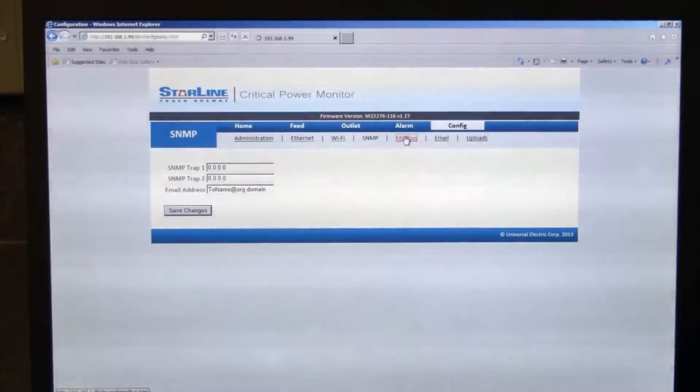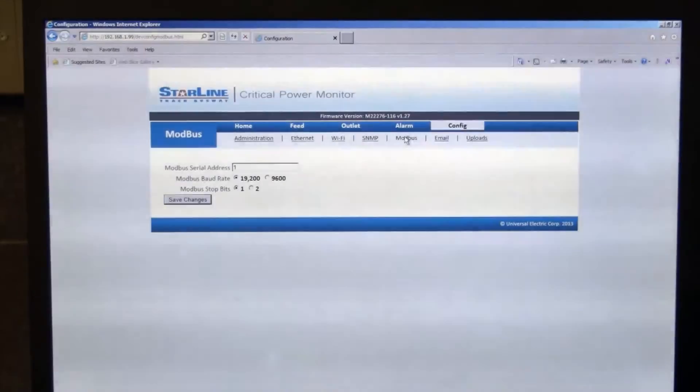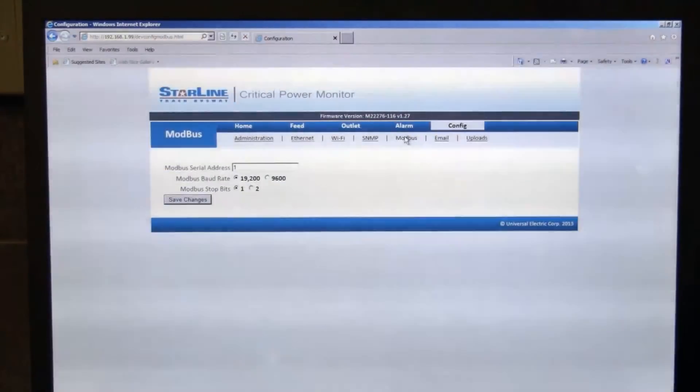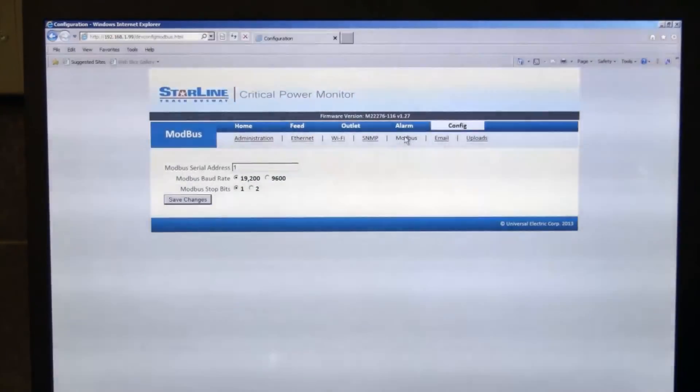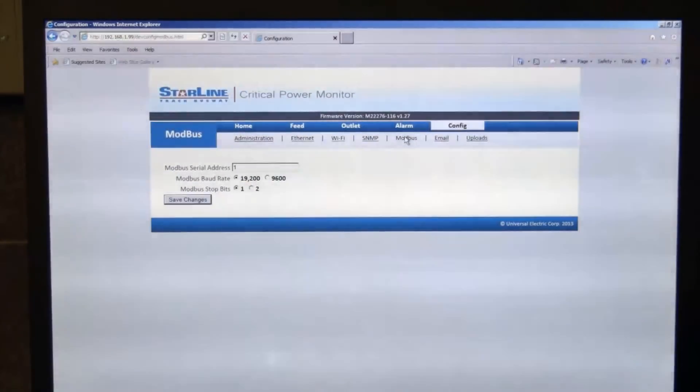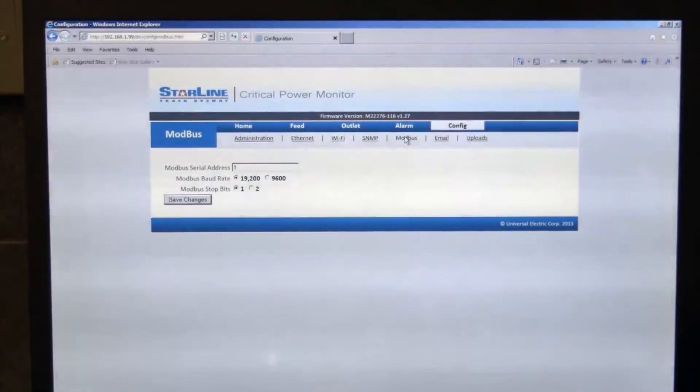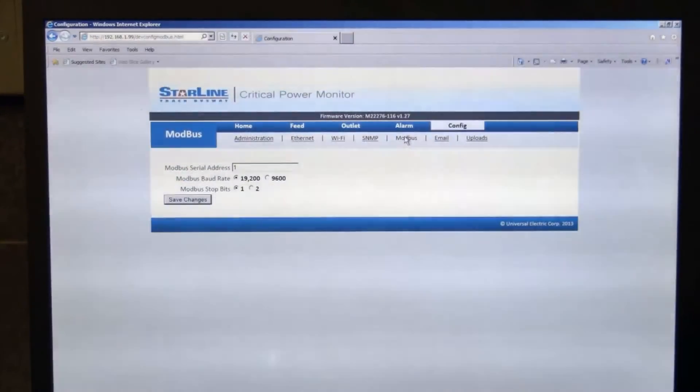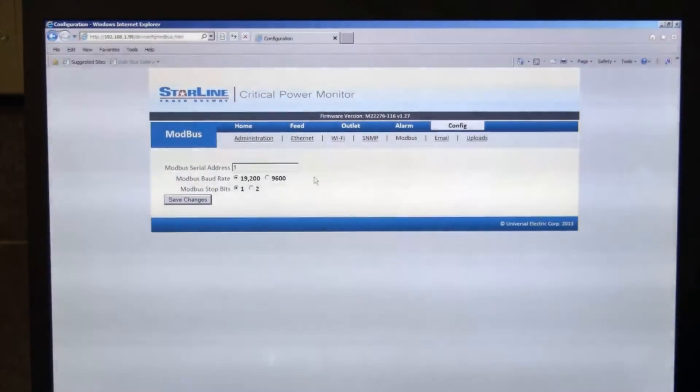Next tab is the Modbus tab. This is where you can set your Modbus address. So 1 to 247. You can also set the baud rate of your Modbus network, either 19,200 or 9,600 baud. And then you also have the ability there to change the stop bits from 1 to 2.